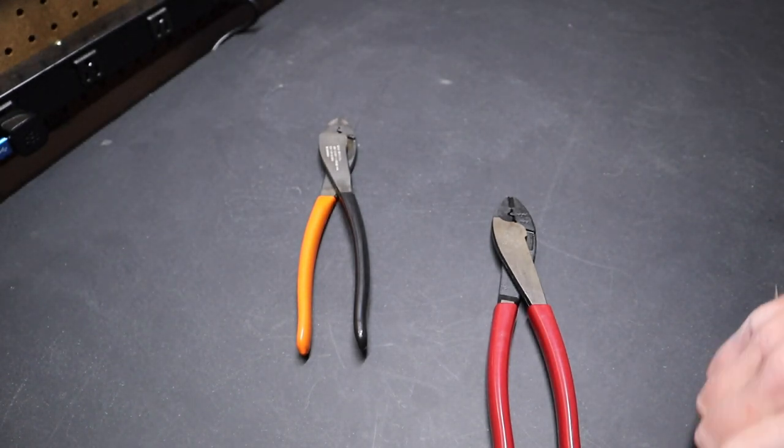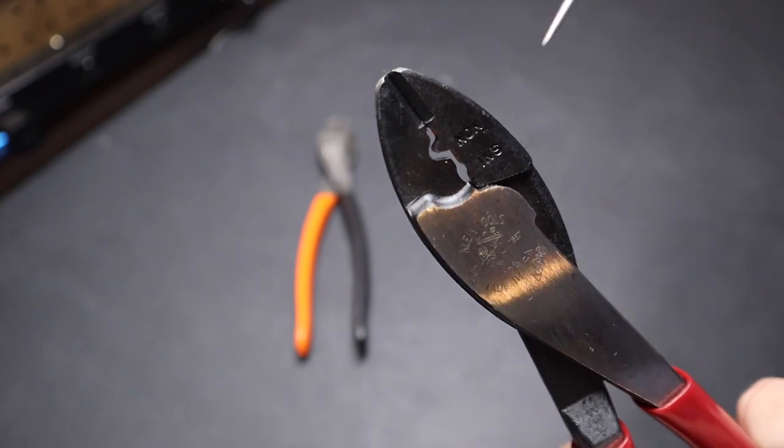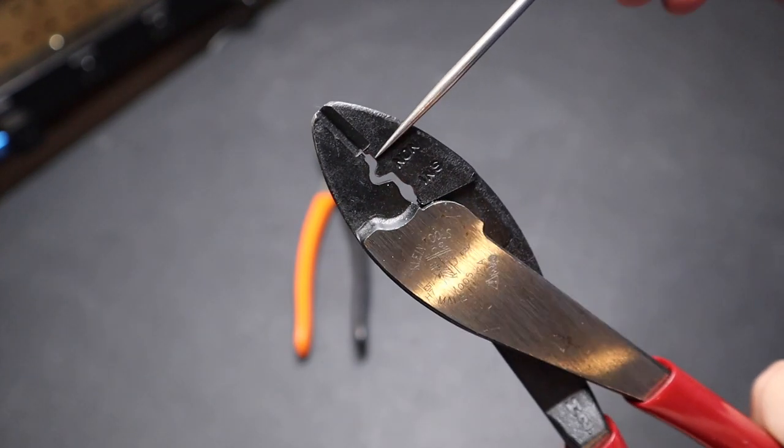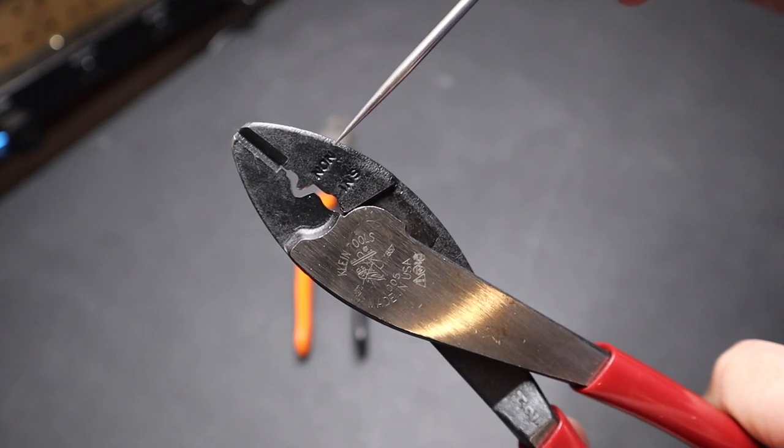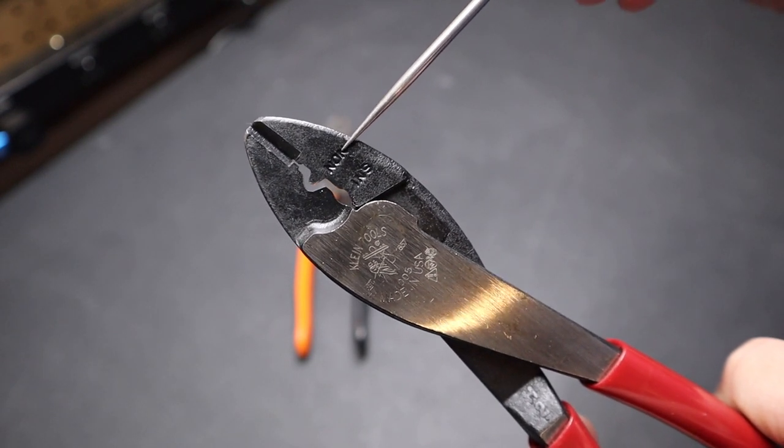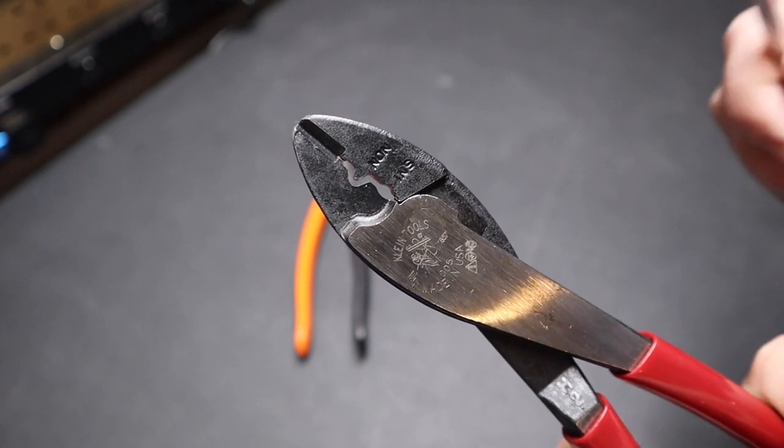Well, what I've seen repeatedly, as everywhere I've seen, including recently on a job, is that folks have been using this non-insulated part of the die for everything they crimp, regardless of whether it's insulated or non-insulated. They like this type of crimper.